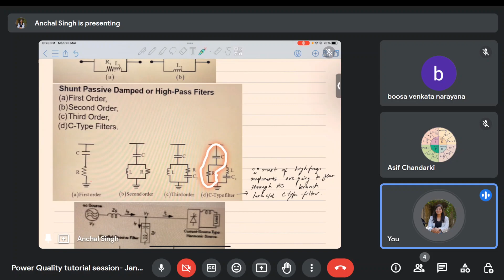It is called C type because this part is used for tuning a particular high frequency, but when that part is not working, for all the higher frequency components this RC branch will always be active. This is a generic branch for all high frequency components, while the other branch is specific for some dominant harmonic.